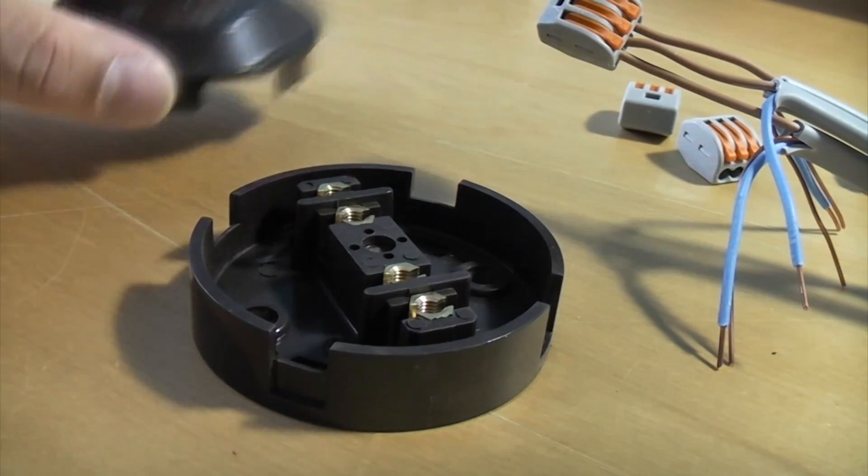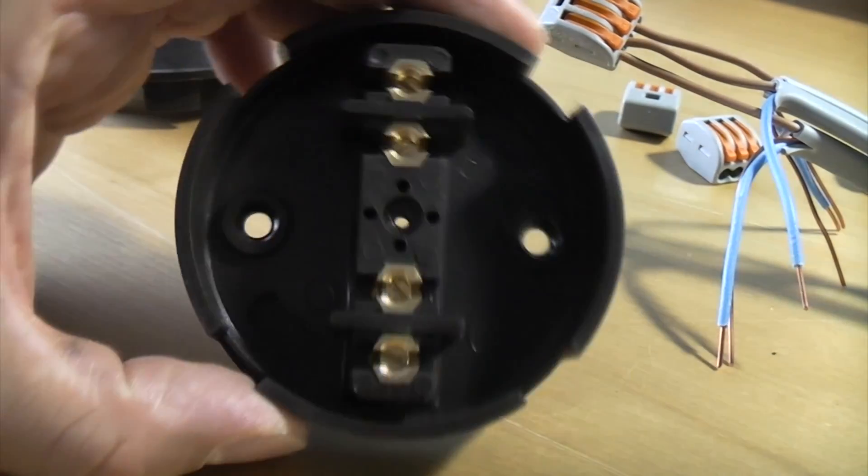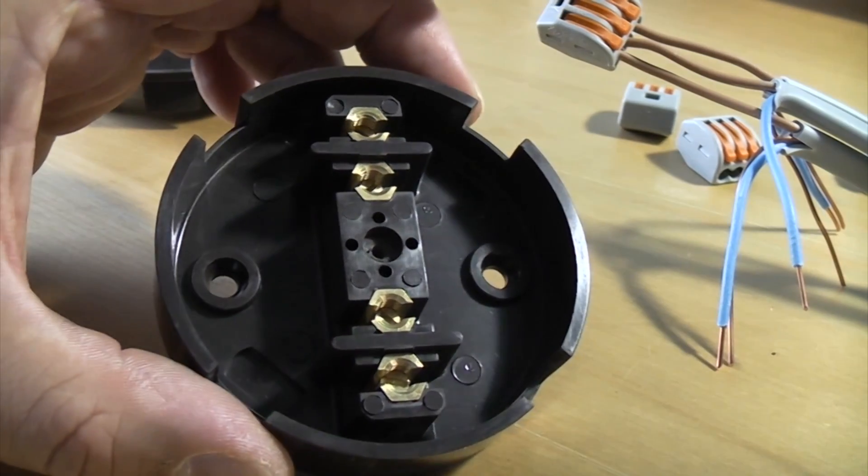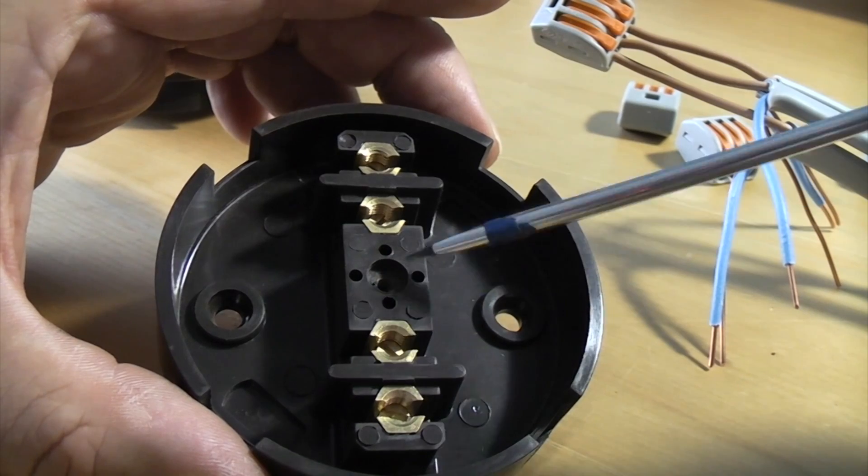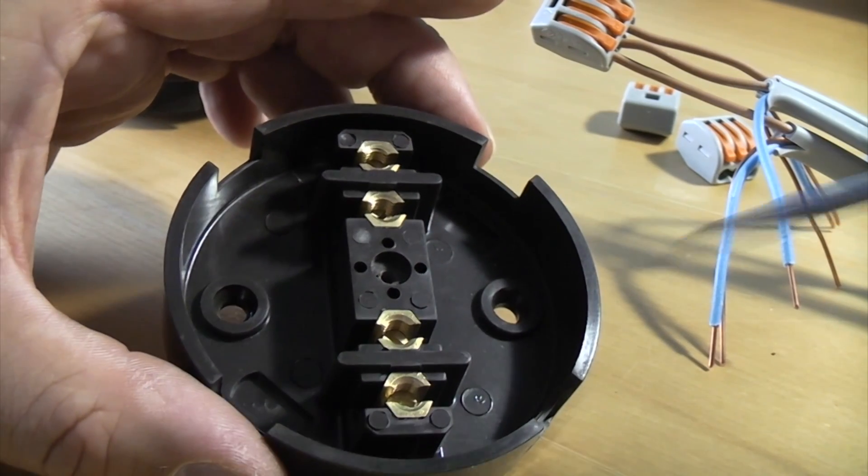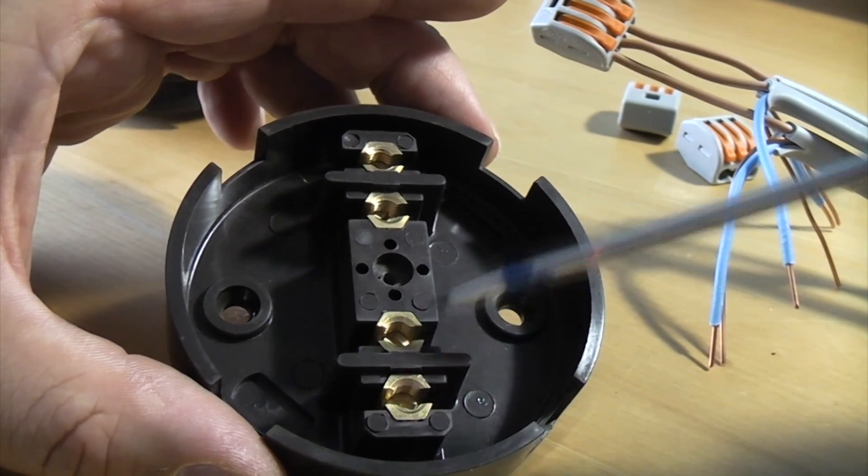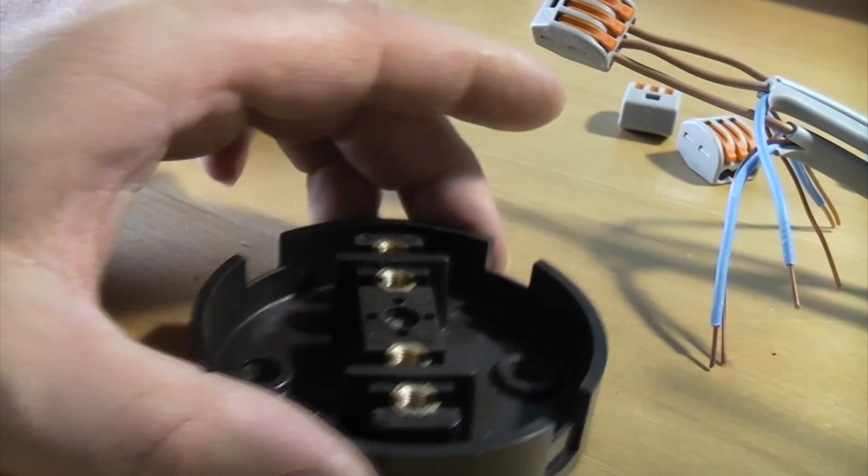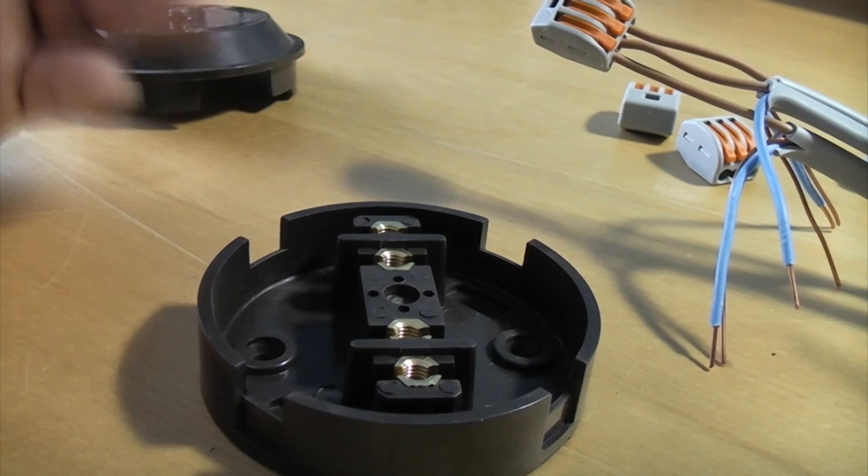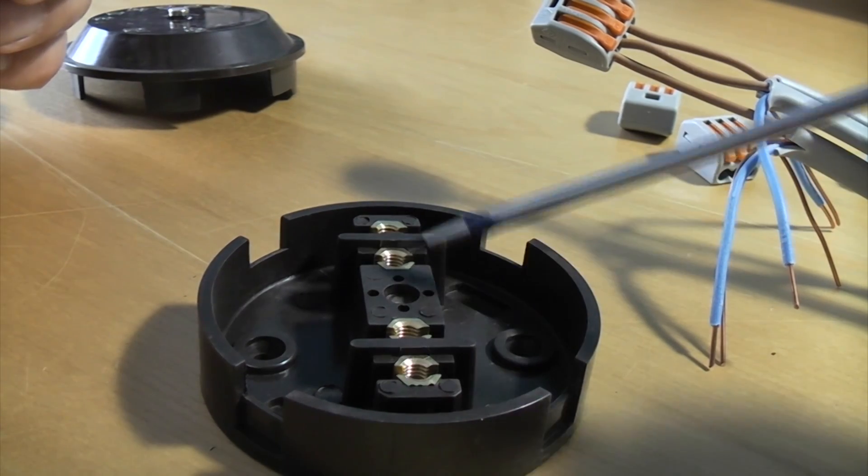In years gone by, you'd often find junction boxes like this being used, which aren't very good. They did the trick, but the problem is because the terminals are brass, it was easy to strip the terminals if you over-tighten them. Theoretically, they still need maintaining, so they have to be left in an accessible place where you can check that the terminals are tight.